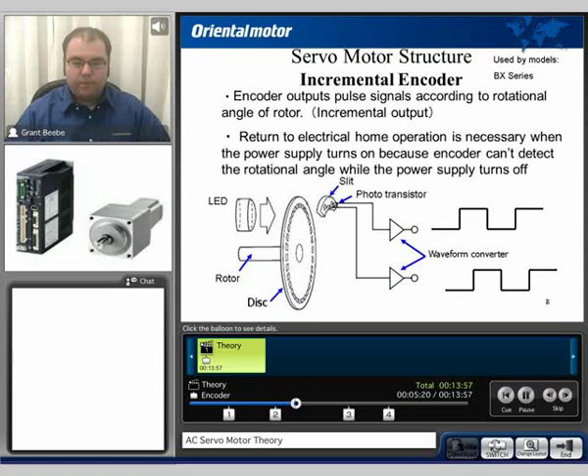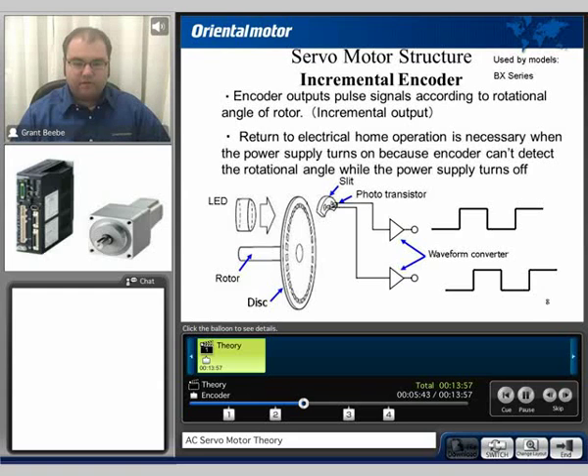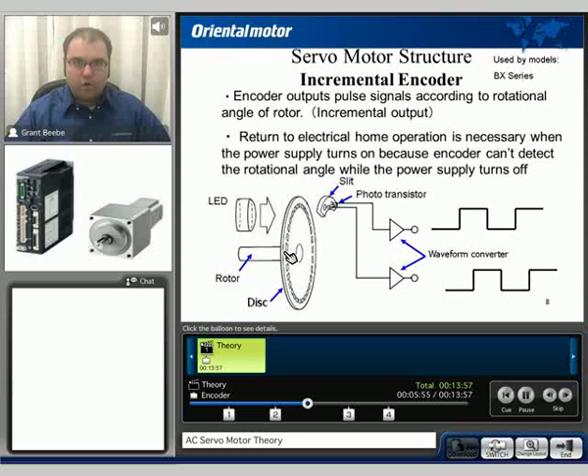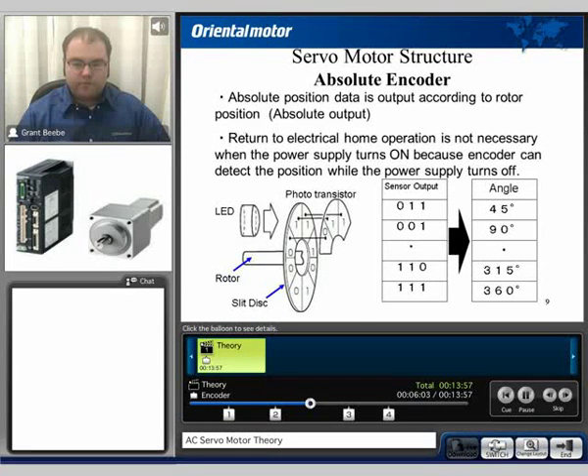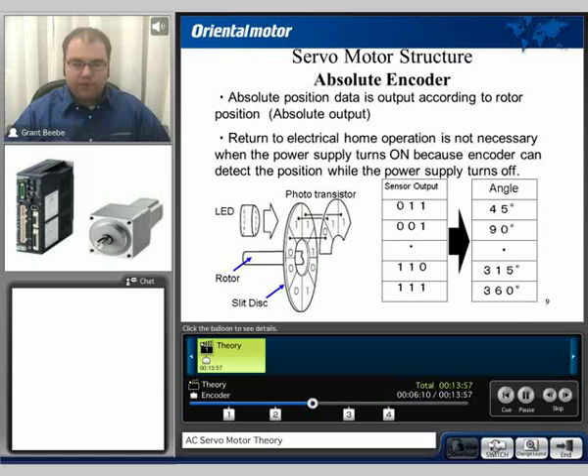With an incremental type encoder, a return to electrical home operation is necessary when the power supply is turned off, simply because most of the time that information is stored in some type of volatile memory on the drive. However, with an absolute encoder that is not necessary, because the information is specific to the actual fixed angle of the rotation of that disk. With an incremental encoder we just have a number of slots all the way around to equal a certain amount of information — be it 500 counts per rev or 1,000 counts per rev. With an absolute encoder it's more specific: we take specific information stored on that disk in usually a binary type scheme to specifically identify the angle of rotation of that disk.